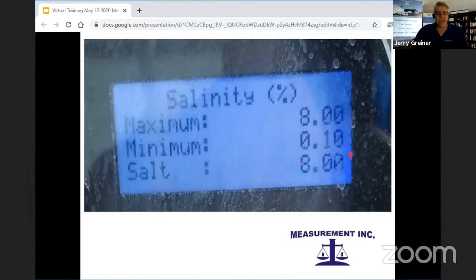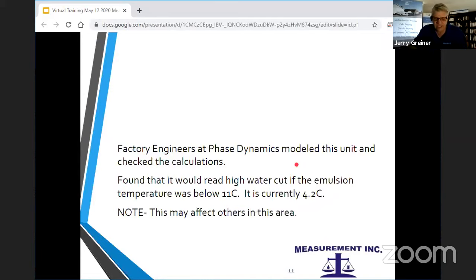So that ended up being a clue to us. It was set at the highest number that it could be, 0.1 to 8, and it's set at 8.00. So what we ended up doing with this unit is getting the factory engineers at Phase Dynamics to model it. And they checked all the calculations. They found that it would read high if the water cut temperature changed below 11 degrees Celsius.